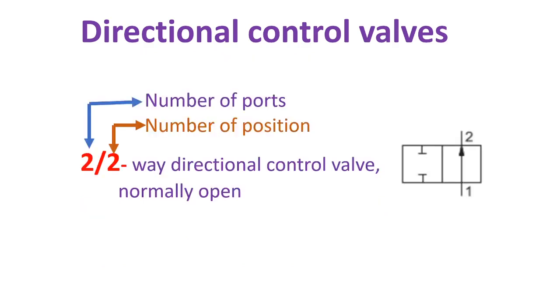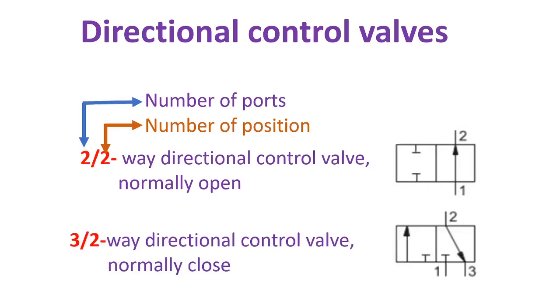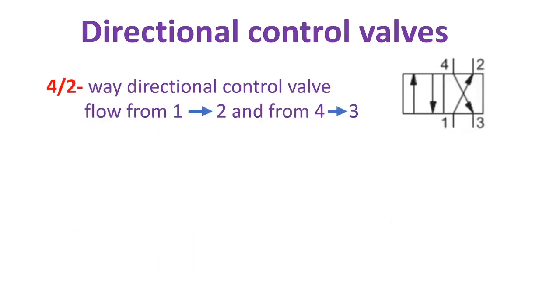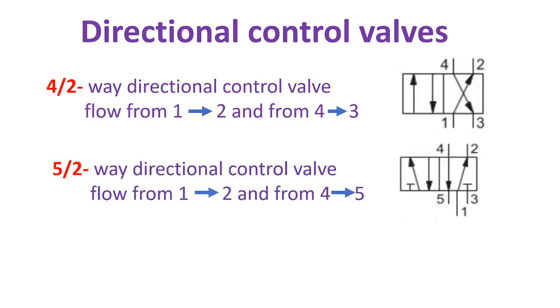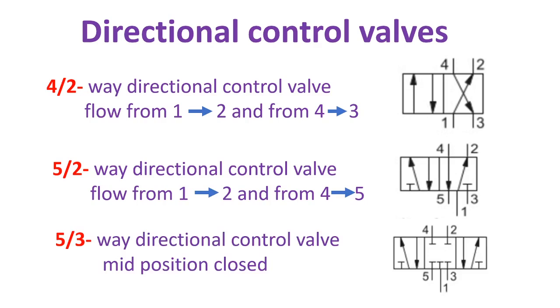The first number represents the number of ports and the second number represents the number of positions. This valve is a two-two-way directional control valve, normally open. The next one is a three-two-way directional control valve, normally closed. Then a four-two-way, with flow from port 1 to 2 and from 4 to 3. Then a five-two-way, flow from 1 to 2 and from 4 to 5. Next, a five-three-way directional control valve, mid position closed.